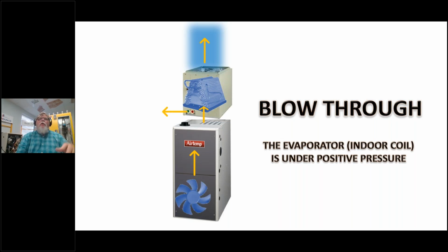It's under positive pressure. Most manufacturers say trap it, but I will just tell you, if you don't trap it, it'll drain because there's pressure on the system. It'll blow the water out of there when that's running. But if you trap it, it's like sealing up the ductwork. Why would you have a 3/4 inch hole in your ductwork letting the air come out when a little trap will take care of that? So that'll generally be the main reason to do that, to save the energy, to save the air pressure, and so forth.